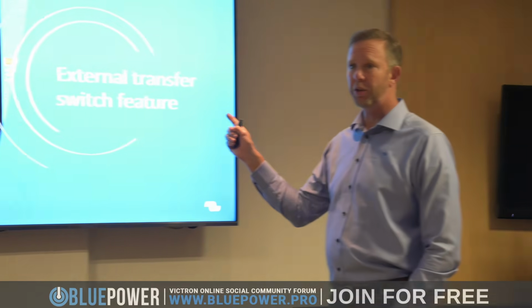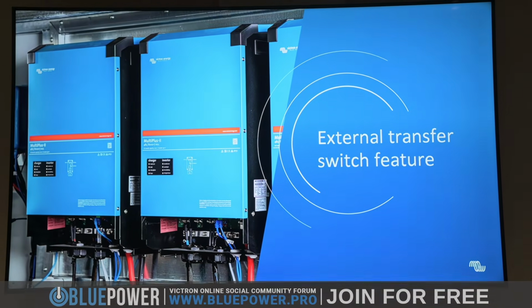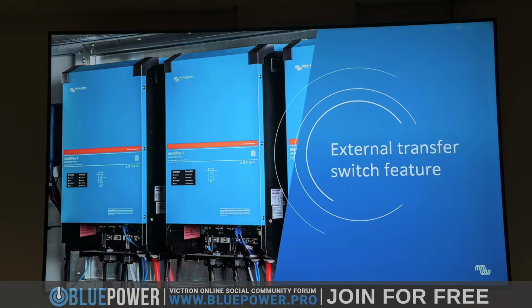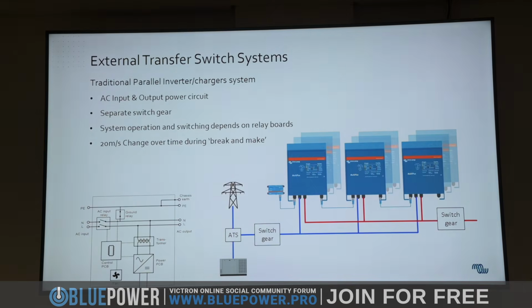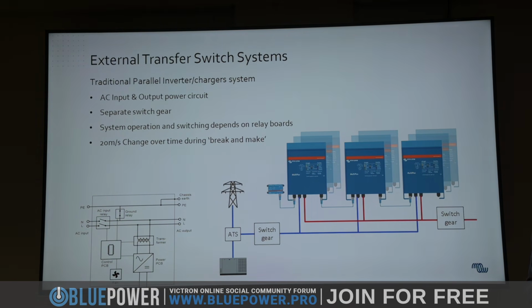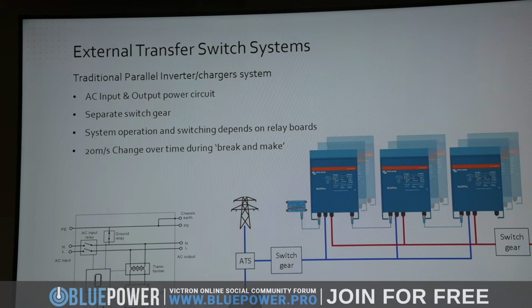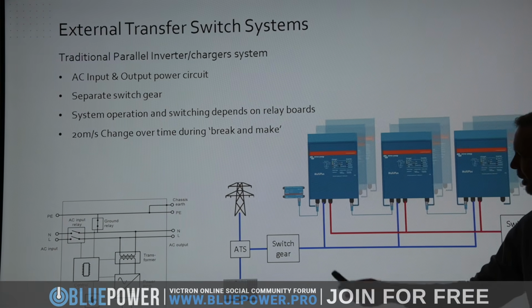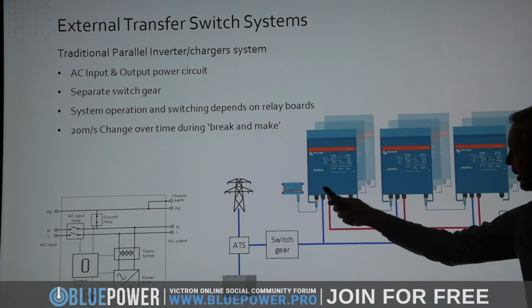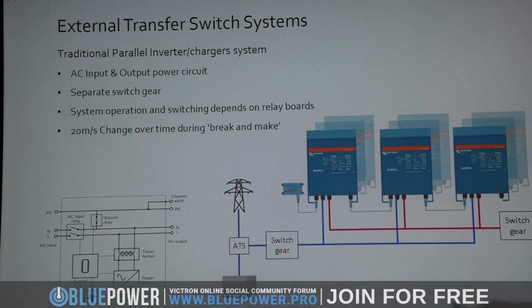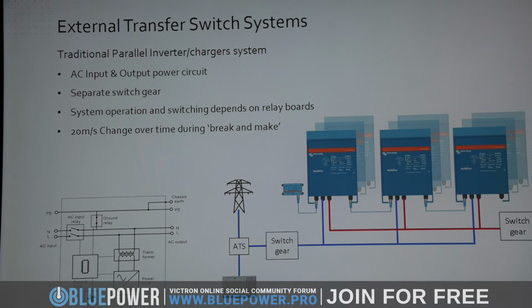Have you guys heard of the external transfer switch? This is the solution we have for the Multiplus 2s, 5, 8, 10 and 15 if you want to do parallel and you want to do big systems. So this is the old school solution. We have our Quattros or our Multiplus units, we have the generator or the grid, and we have our input switch gear coming into each one. Then we have our outputs going to the output switch gear to the system.